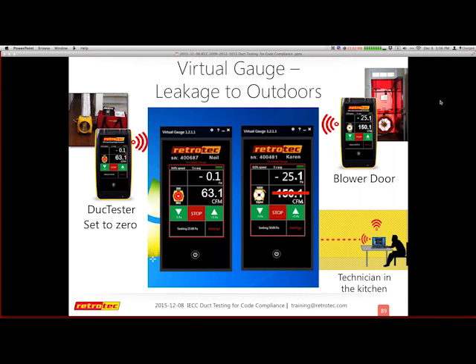Probably not, but to me, there are always just things that I do out of habit. If you always have good habits, then you continue to do good habits. So if I forgot to open up a window, then maybe next time I'd forget again. I always just start with, okay, this is set up, and then my tubing's set up. I open a window and I touch the gauge. Older homes probably don't really have that much of an issue either, because they're so leaky. So mostly it's for tighter homes, but I guess it's your call as to whether or not you feel you need to do that. But in general, the best practice is to always make sure that your ducts are open to the outside. And if there's no drywall separating them from the attic or crawl space or any other conditions, because it's wide open, then there's clearly nothing to do for a hatch, because you don't have one. Anything else that you had, Jay?